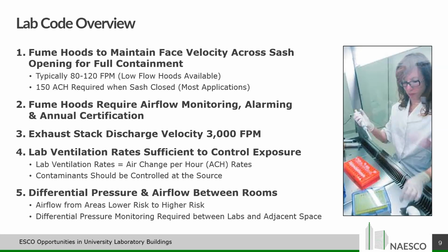And when you close the sash on a fume hood, there's another code requirement, and that's you can reduce the CFM, but you need to maintain 150 air changes per hour inside of that hood. And that's a recent change. It used to be more, and we'll hit that in a few minutes here. But that 150 air change per hour closed sash is a code requirement at a minimum. Now, also with your fume hoods, you are required to have a monitoring device that is measuring that face velocity across the opening. And should you fall out of an acceptable range, it needs to alarm, warning the user that that fume hood is no longer safe to use.